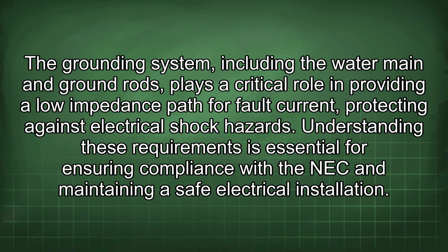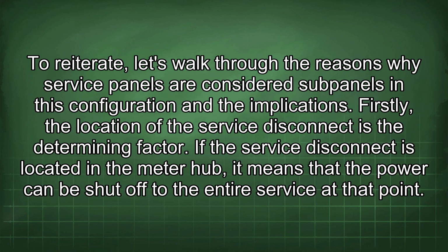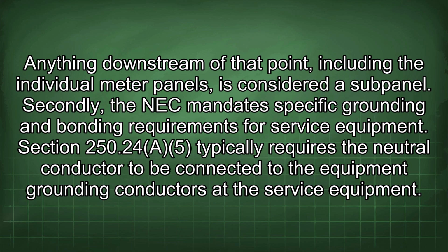Understanding these requirements is essential for ensuring compliance with the NEC and maintaining a safe electrical installation. To reiterate, let's walk through the reasons why service panels are considered subpanels in this configuration and the implications. Firstly, the location of the service disconnect is the determining factor. If the service disconnect is located in the meter hub, it means that the power can be shut off to the entire service at that point. Anything downstream of that point, including the individual meter panels, is considered a subpanel.